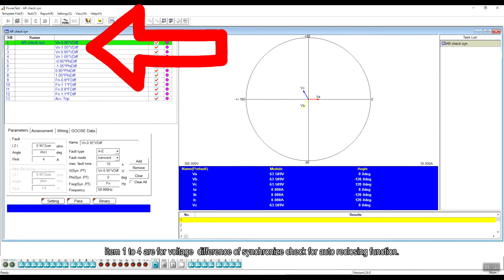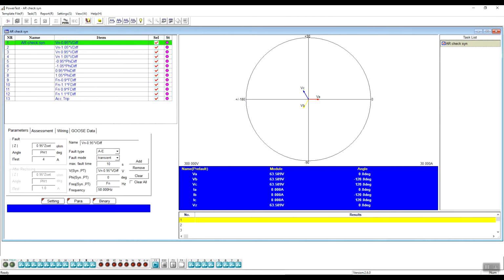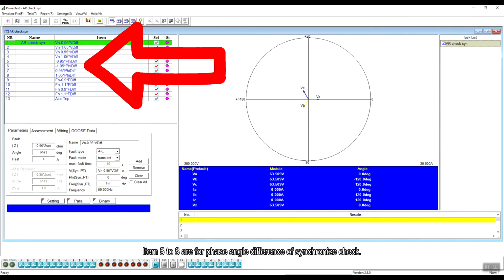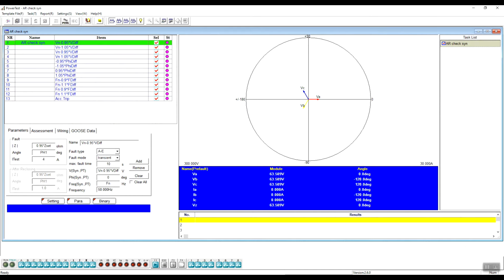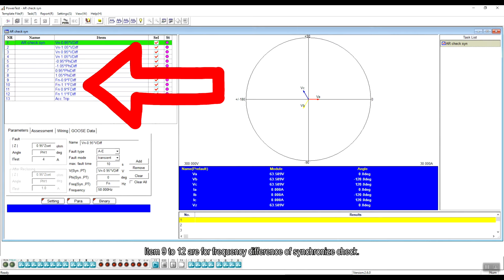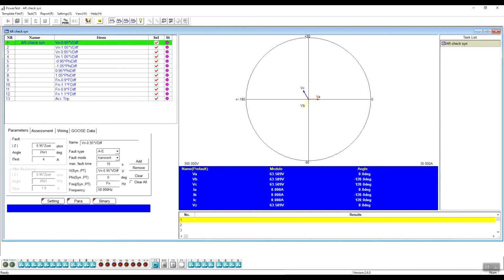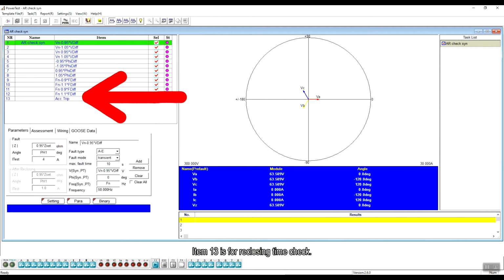Item 1 to 4 are for voltage difference of synchronized check for auto-reclosing function. Item 5 to 8 are for phase angle difference of synchronized check. Item 9 to 12 are for frequency difference of synchronized check. Item 13 is for reclosing time check.